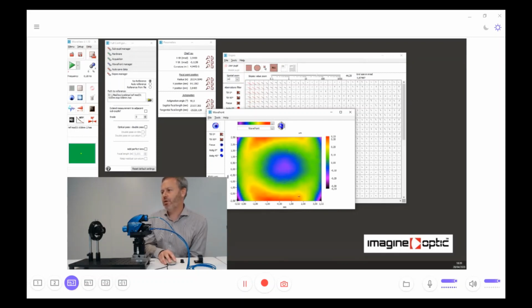So if we extract from this information only the center, it will be of course smaller, in the range of 40 or 50 nanometers root mean square. And I'm very confident in saying that this aberration does not affect the measurement of this lens here, because it is included in the reference, and again it is subtracted.